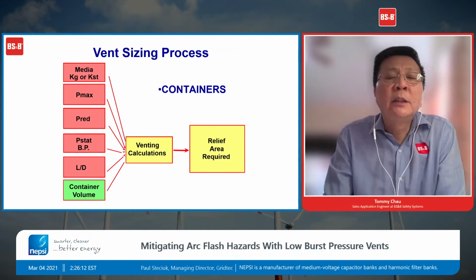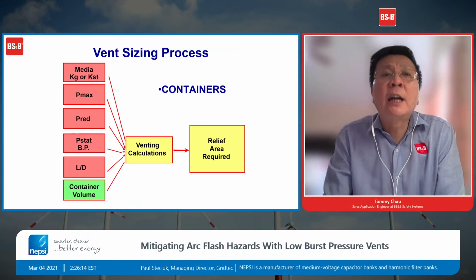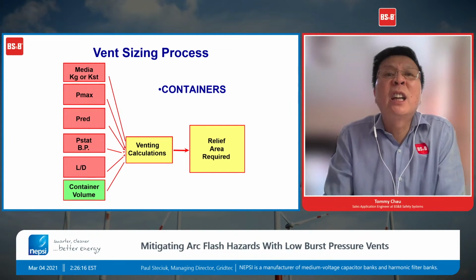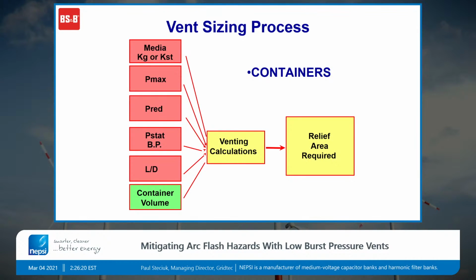So here are some of the parameters I would require to do the sizing calculation for you: the type of dust that you have, the KST value, or the KG value if you have a gas application. Then, as we talked about earlier, the Pmax value, the Pred, and the burst pressure of the explosion panel, the L over D information, and obviously the volume of the equipment.